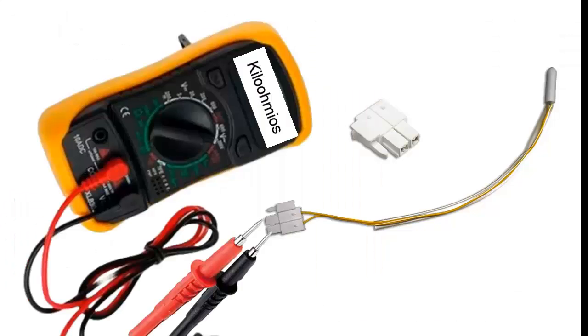Remember to check temperature sensors by disconnecting them and using a multimeter in the kilohm scale to measure their electrical resistance. The measured value on the multimeter should never be 0 or infinite. Additionally, the electrical resistance value should decrease when the sensor tip is rubbed with the hand. If you have the equipment's catalog, check if it has the sensor's resistance versus temperature table to compare the measured values.